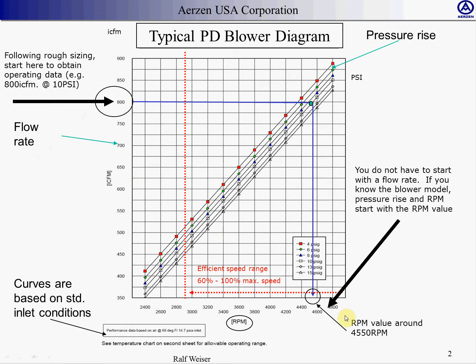That works in reverse as well. If you know what model number unit you have, and you know what pressure you have, and you know what the speed is, you can draw the same line the other way. Let's say you have a 4,000 RPM machine at 15 psi — you could draw this line over here and you would roughly have like 660 or 670 ICFM.